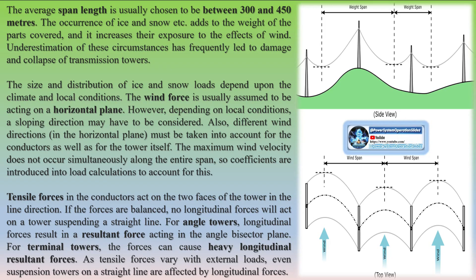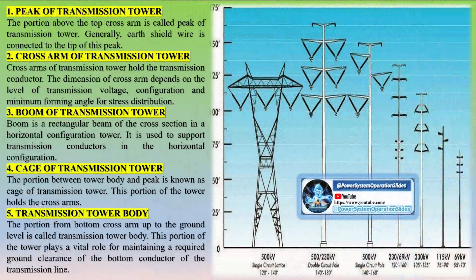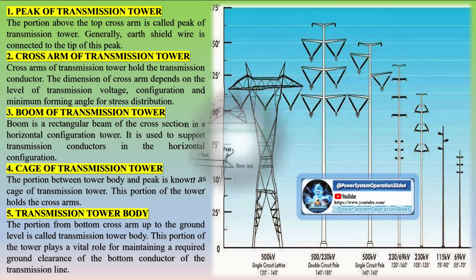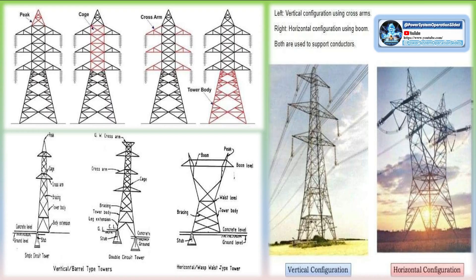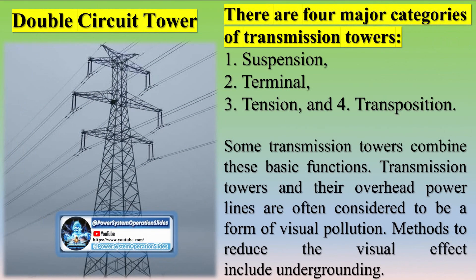Transmission voltages are usually between 23,000 volts to 765,000 volts. Transmission tower conductors are usually manufactured from steel-reinforced aluminum cable (ACSR — aluminum conductor steel-reinforced) and are almost always arranged in sets of three for three-phase alternating current transmission. A fourth neutral cable may be used for transmission over short distances, but this is not common. Conductors are grouped by phase — there could be one conductor line per group (three total), two conductor lines per group (six total), or more. Groups are installed in multiples of three and may be arranged in a triangular shape or parallel to each other, with three-way grouping increasing transmission efficiency.